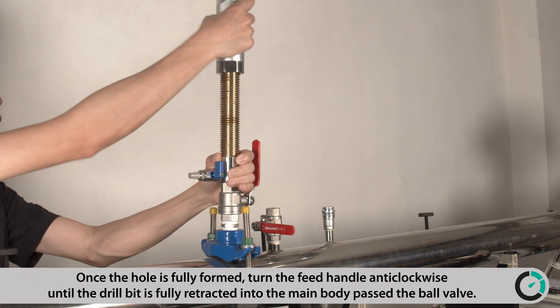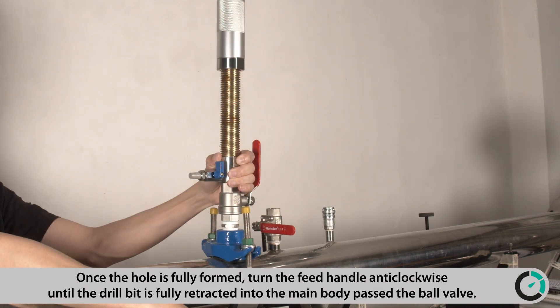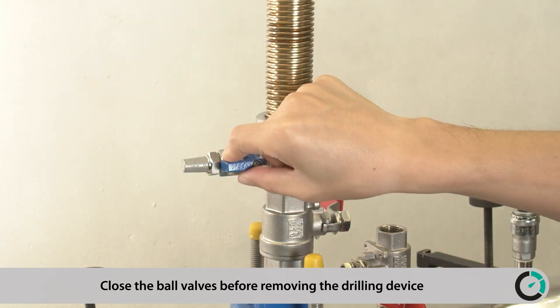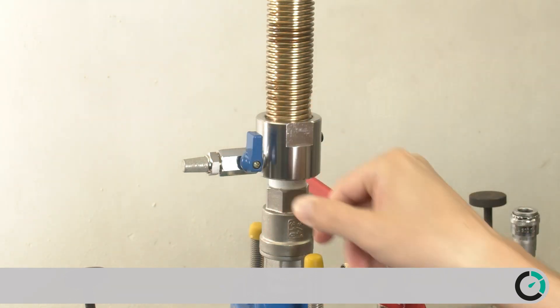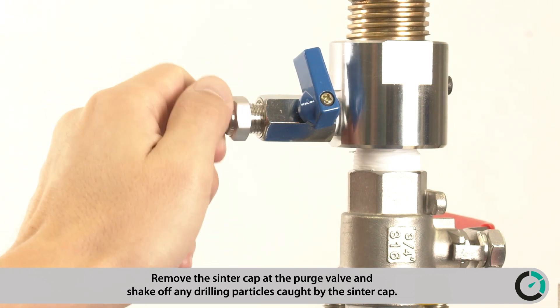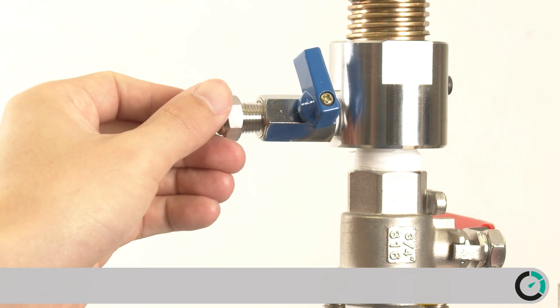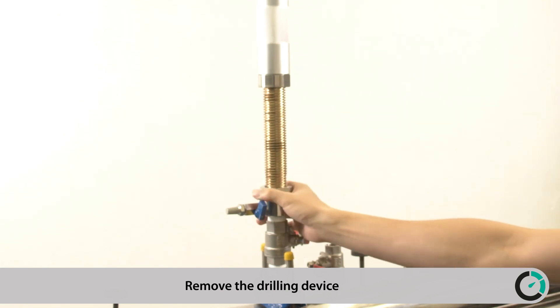Once the hole is fully formed, turn the feed handle anti-clockwise until the drill bit is fully retracted into the main body past the ball valve. Close the ball valve before removing the drilling device. Remove the sinter cap at the purge valve and shake off any drilling particles caught by the sinter cap. Remove the drilling device.